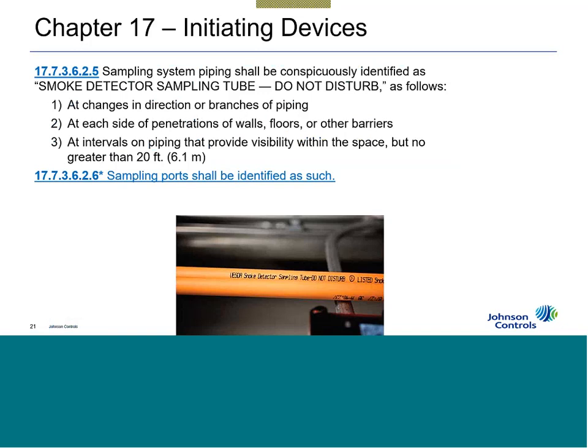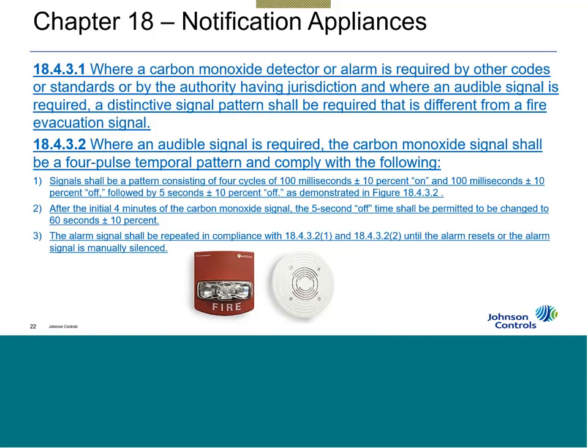In some cases, you walk into some buildings and you see the holes, and they're every 30 feet or so, and you kind of know what they are because you're in the business, but an average person wouldn't know that. And then also the ports need to be identified, and the piping needs to be listed. There are still many, many cases where people buy the equipment and then run down to the supply house and buy regular old PVC piping or conduit and use that as their piping for their air aspiration system. Can't do that. It's got to be listed for that usage.